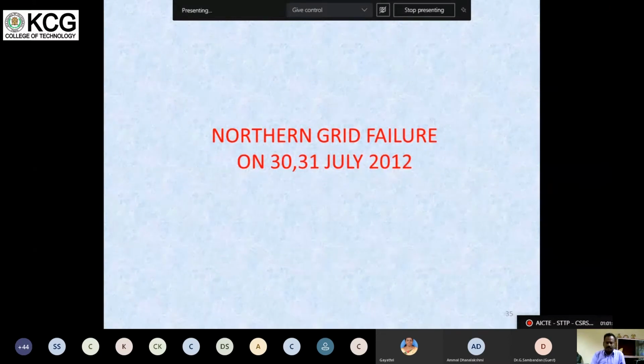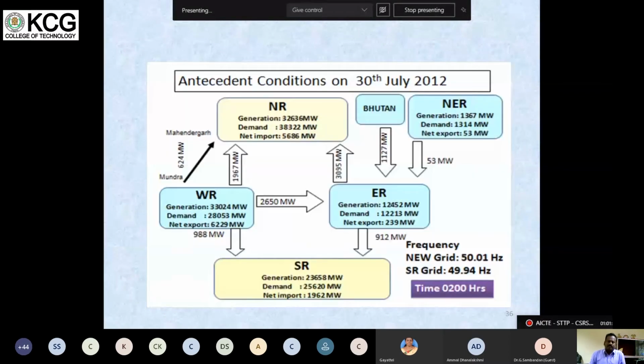We throw light on the northern grid failure which happened on 31st July 2012, and this is the condition. The northern grid was with a generation of some 32,000 megawatt. The time is 2 o'clock in the morning, 30th July 2012. The demand at that particular time was 38,000 megawatt. So import was happening, around 6,000 megawatt. It was going, you can see in the figure, from WR to NR, that is, western region to northern region.